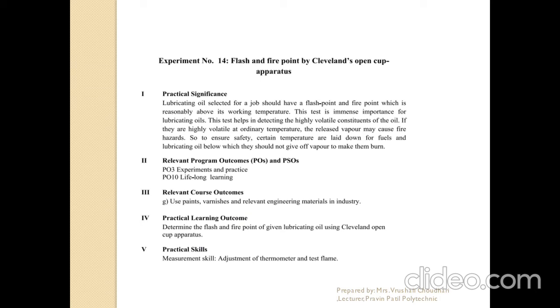This finds out the highly volatile constituents of the oil. If highly volatile constituents are present in larger amounts, the oil will catch fire easily and that is hazardous. To ensure the safety of the machinery, we have to check the working temperature of the lubricating oil, which is based on the flash and fire point.